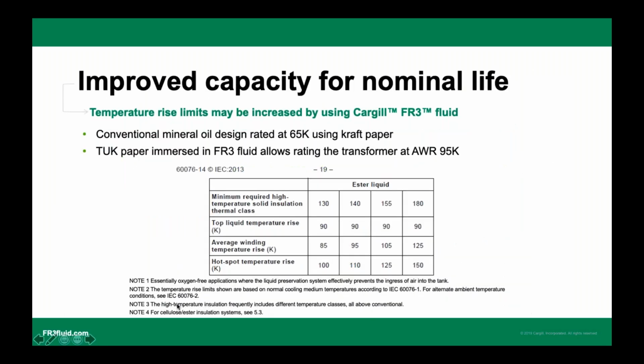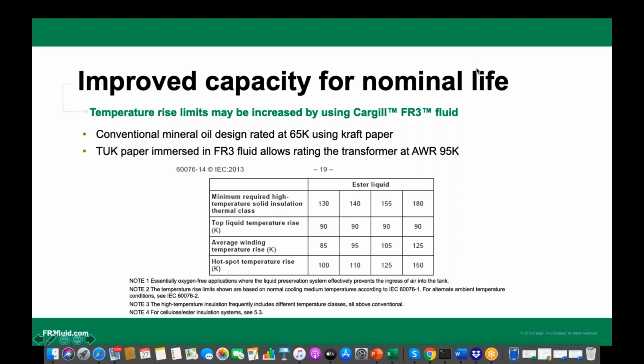If somebody wants to understand the table details, I will just try to explain in short. The basic kraft material, even though it has a thermal class of 87 degrees C or 85 degrees C, when it's impregnated with mineral oil, which has a thermal class of 105, typically becomes a class 105 composite insulation system. Same way, when you have a natural ester K class, this data again is from FR3 data, and natural ester fluid is impregnated with conventional kraft paper, it becomes a thermal class of 120, and if the paper is thermally upgraded kraft, it becomes 140. So that's how the thermal class in numeric values has been specified in the standard.